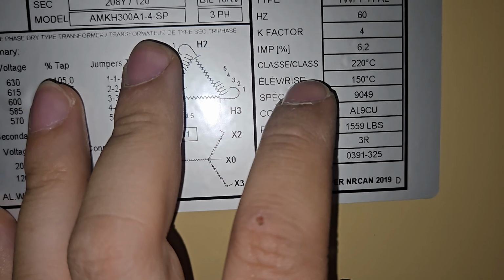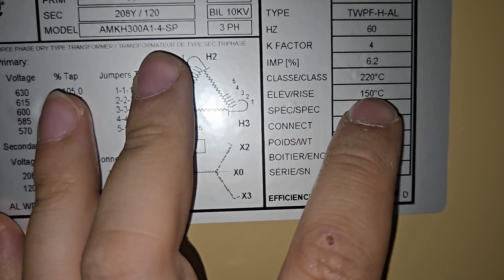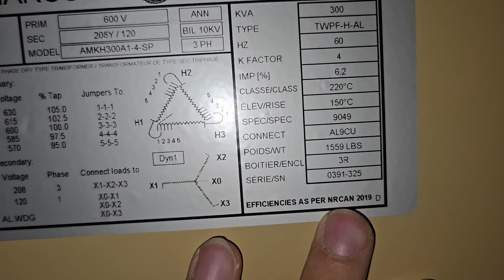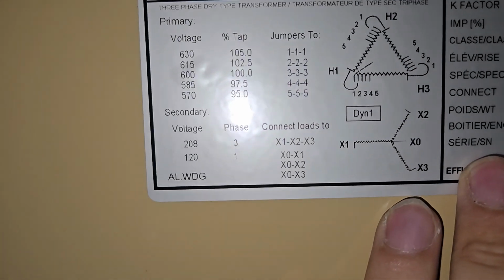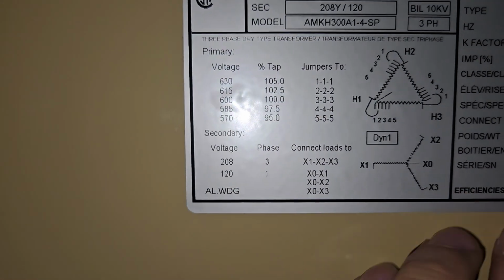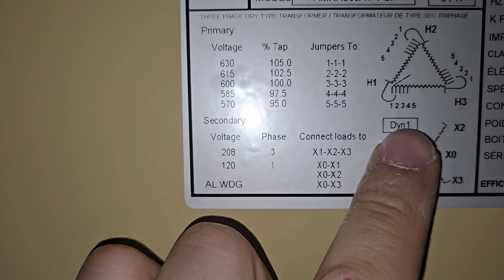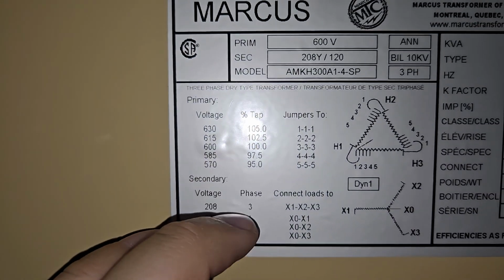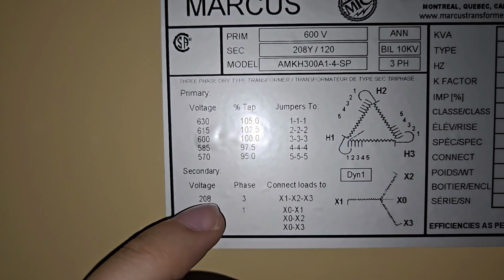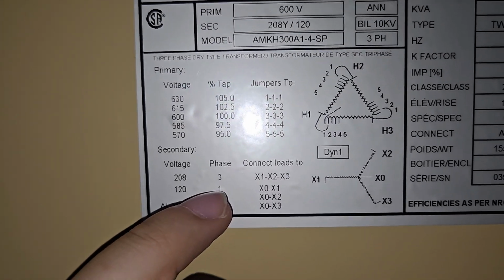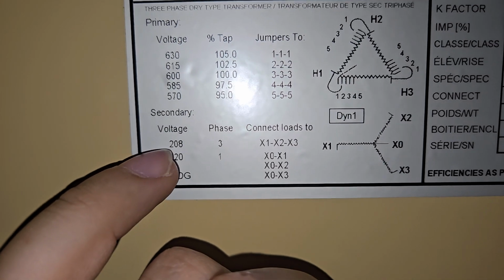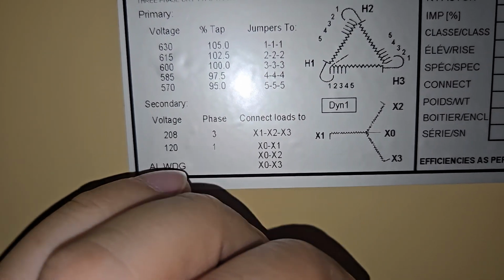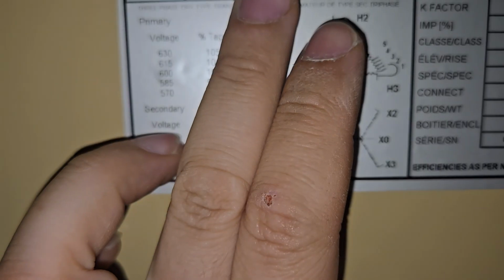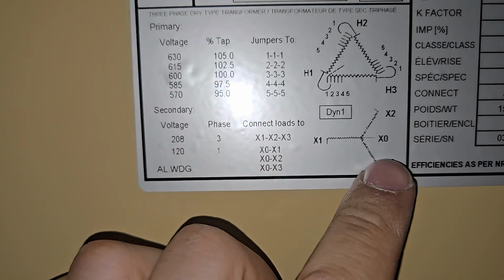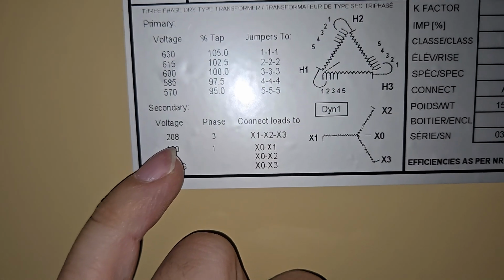Now this one's in French though, so you can see like this is designed. It can take a temperature rise of up to 150 degrees. They do get very hot. Now, when you wire this thing up, you're going to see primary voltages and secondary voltages. So normally, your secondary is what's coming out. Now, some of these work two ways. So you can take 208 volts and turn it into 600 volts if you wanted to.